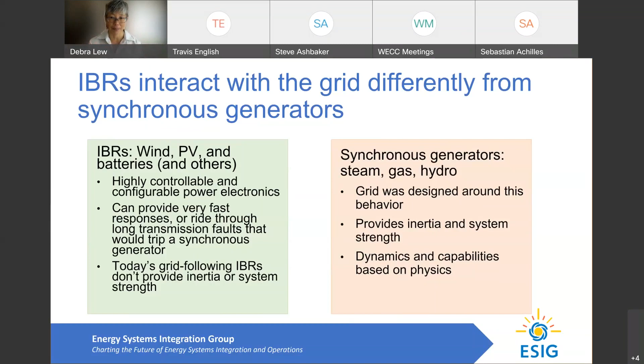Conventional synchronous generators - your coal, gas, hydro plants - provide inertia and system strength. While they have controls, their dynamics are dominated by their physics, as opposed to the IBRs, which are dominated by how you program them. Now, grid forming inverters are a promising technology to get the best out of both of these worlds, and that's what we're going to talk about today.